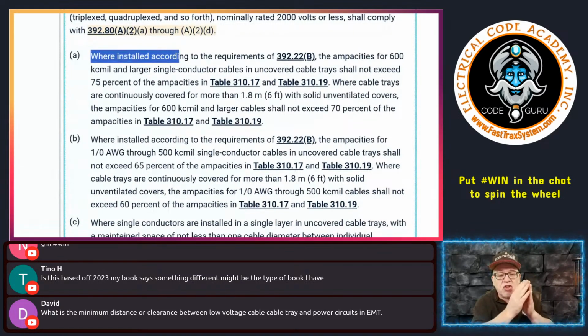So this assumes we're installing them in accordance with the rules, whether it's a single layer or based on fill, which you could stack. However you do it, we installed it in accordance with this requirement. Now, it says if we followed the rules for putting these conductors in the cable tray, then the ampacities for 600 kcmil and larger single conductor cables or single insulated conductors in uncovered cable trays, just a normal open uncovered cable tray, whether it's a rung style or ventilated bottom or ventilated trough, it's open, right, uncovered.